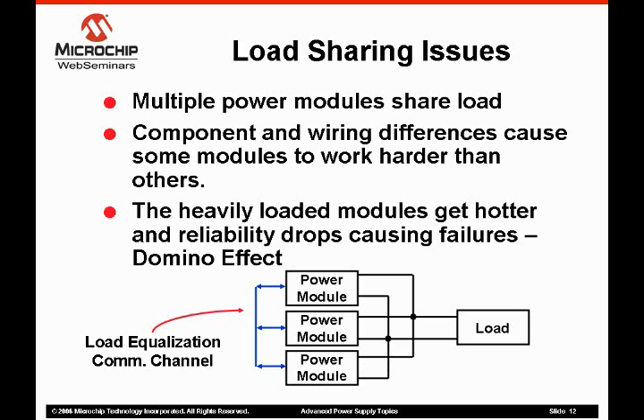A slow analog or digital communications link passes information among the modules to force the output voltages to a common value to enforce load sharing. The control loop is slow, working on a thermal time constant basis.